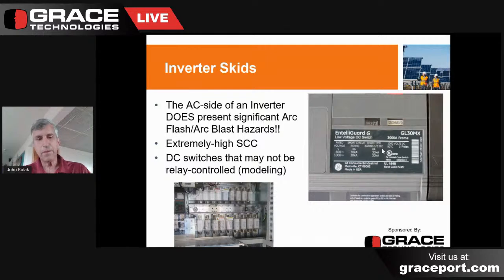And then the picture on the lower left side is on the DC side of the system. These are going to be where the combiner boxes come in, when they come in from the combiner boxes into the inverter. And we'll talk a little more about that. But remember that picture in the lower left side, that's going to come up more than once.